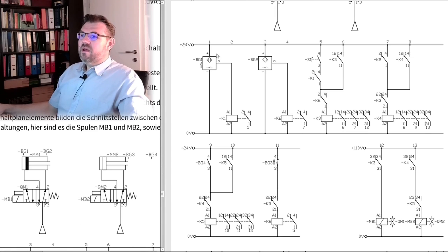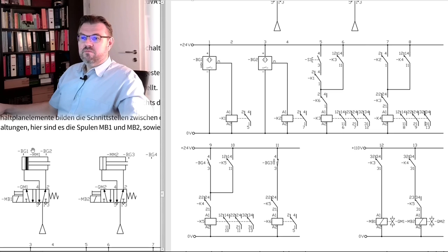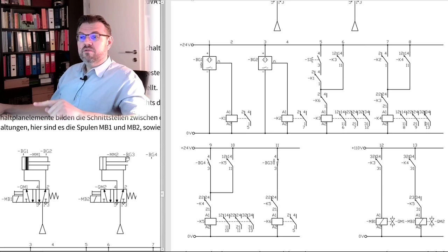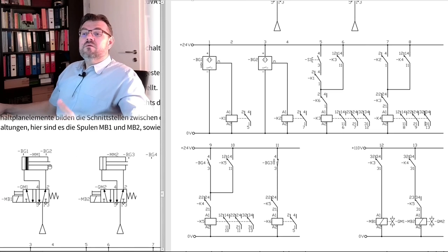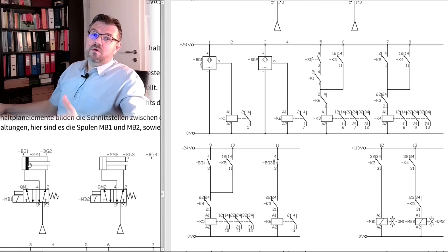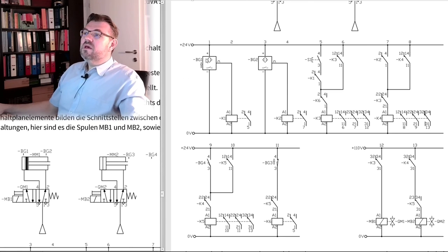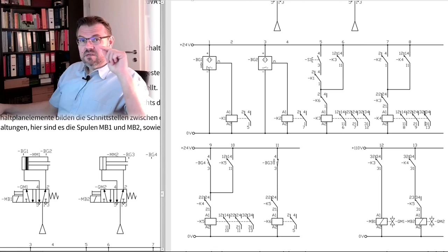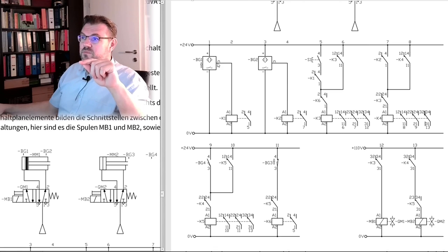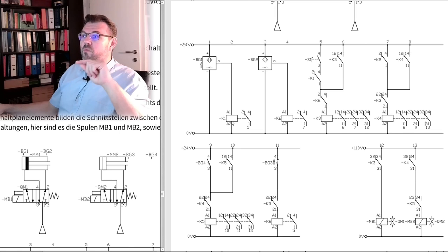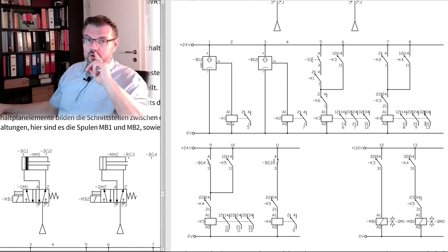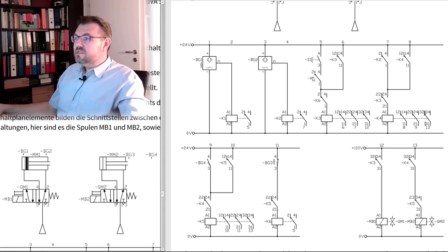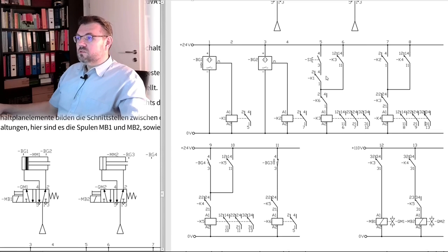What is written there, actually, is that BG1 and BG3 are operated. If we look where BG1 and BG3 are, both cylinders are traveled inside. So BG1 is operated. If BG1 is operated, this is a proximity switch. This means we have here a signal, and in part number 2, we are operating K1. So K1 is operated. So this here, actually, in this part, it is closed.